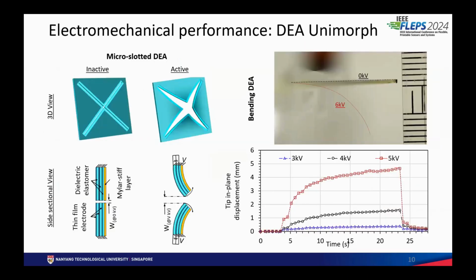And as I mentioned before, we try to use the bending form of dielectric elastomer actuator for this device. And this is how it looks when we activate the device. Here, the video shows only one section of this cut. We have some form of dielectric breakdown when we apply voltage above 6 kilovolts. So for all our applications, we try to restrict the applied voltage to below 5 kilovolts, and we are able to obtain quite good tip displacement. The maximum tip displacement we can obtain at 5 kilovolts is about 5 mm.